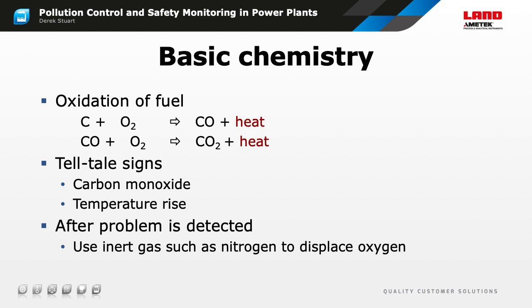When spontaneous heating is occurring, the combustion is inefficient and only proceeds to the first stage. Therefore, the telltale signs of spontaneous heating and spontaneous combustion are the emission of carbon monoxide and a rise in the temperature of the fuel. Once a problem has been detected, the site operator can take steps to neutralize it, generally by using an inert gas to displace the oxygen or by removing the fuel from the storage area.